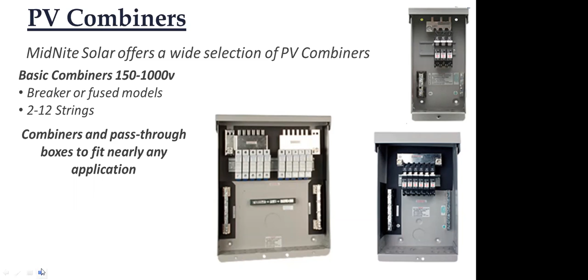And so in your mind, you would think that's a bad thing, but there's no problem with that. That was fully tested by UL. The reason we have a polarity is repeated use. These breakers are rated as a switch as well. So if you use them 10,000 times in that case, you may get a little more arcing on the contacts, and before you know it, you've got a bad breaker. But in a one-time use like that, you'd never have a problem. The good news is these breakers are being phased out over the next year and a half with a breaker that is non-polarized. So then that issue goes away. Well, that concern goes away, I should say. It's not an issue, but the concern goes away.